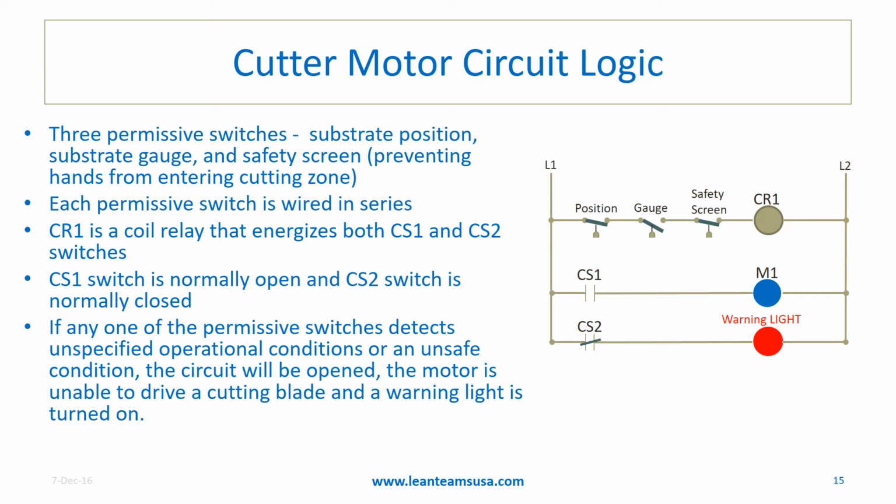The first tool is a schematic of the cutter motor circuit logic, basically how and why the motor works. This is a visual of how a key component functions through certain controls. Not shown here, what I like to do is add measuring points and what these measures should be when conditions are correct. Key component logic is provided by the OEM. The visual is not the provided drawings.